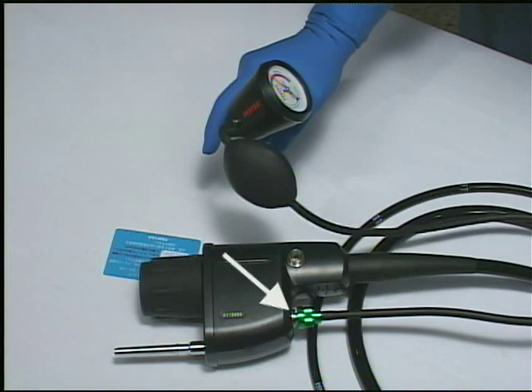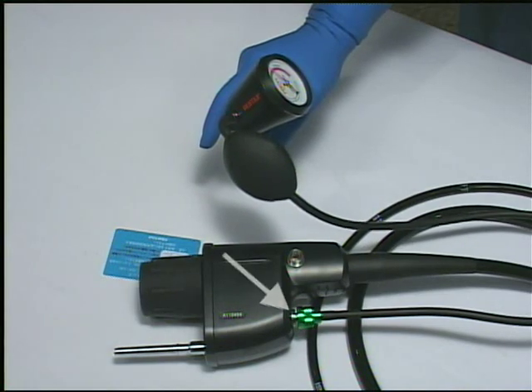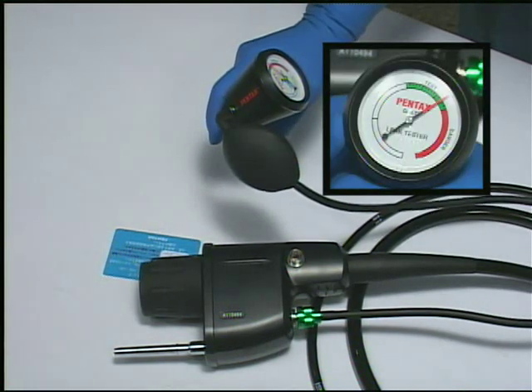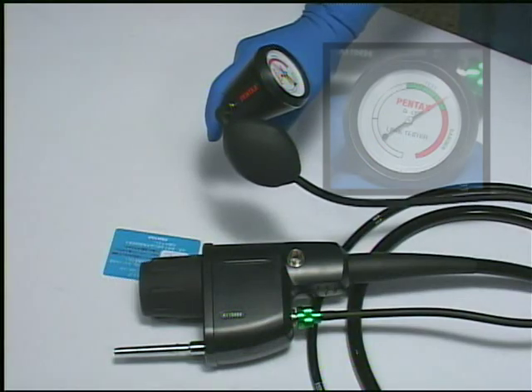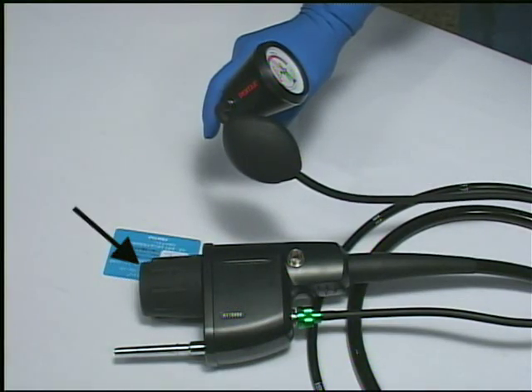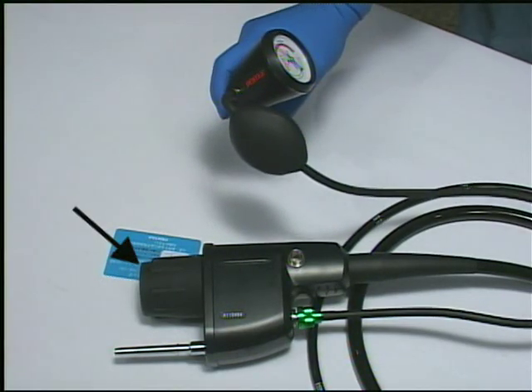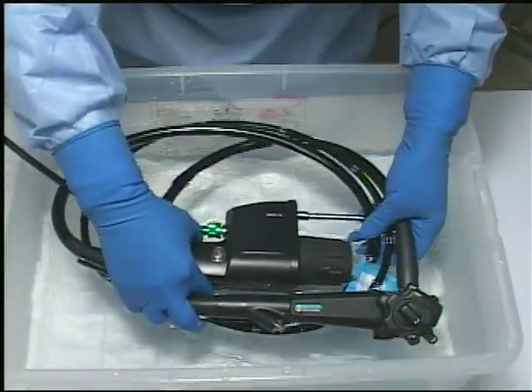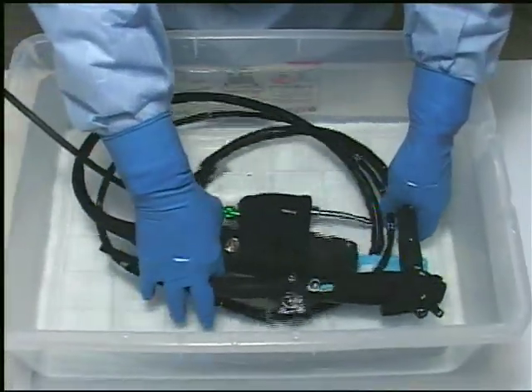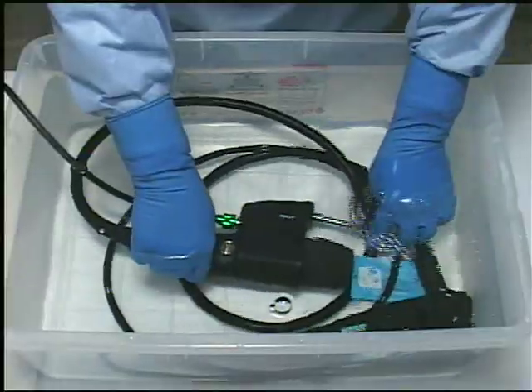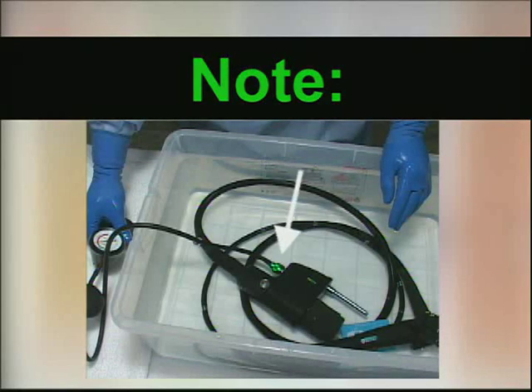With the leakage tester securely attached to the scope pressurized with the gauge indicator in the green zone, and the soaking cap securely attached over the electrical contacts, the entire scope, with all valves and inlet seals removed, may be immersed in clean water. Note: only the leakage tester connector and a small portion of its tubing should be immersed. Never immerse the entire leakage tester.